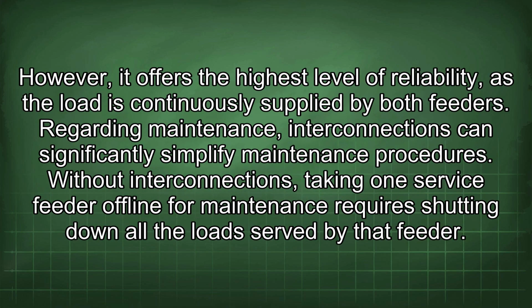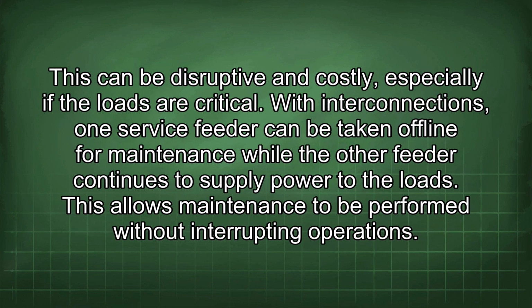However, it offers the highest level of reliability, as the load is continuously supplied by both feeders. Regarding maintenance, interconnections can significantly simplify maintenance procedures. Without interconnections, taking one service feeder offline for maintenance requires shutting down all the loads served by that feeder. This can be disruptive and costly, especially if the loads are critical.